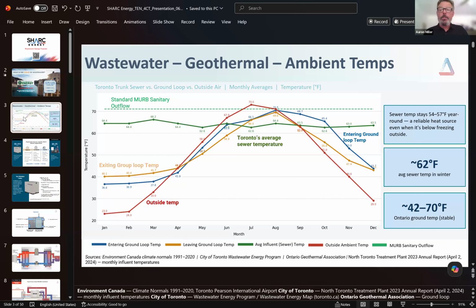One of the reasons why wastewater is such a rich, valuable energy source, in addition to its abundance, is the consistency of its temperature. So here's some temperature data from Toronto. You can see that the red line, which is the outside temperature, dead of winter versus peak of summer, big swings in temperature. And there you can see the orange and blue line, which is really the geothermal loop. It trails the ambient temperature by just a month or so, right? So you have those swings in the geo loop. So you have to get into balancing and making sure you're not taking too much energy out or putting too much in during certain times of the year.